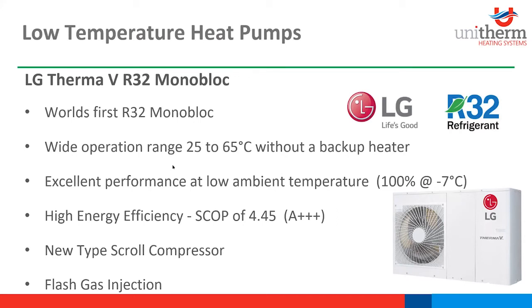So this is a flash gas injection, or wet vapor injection as it's also called. You're compressing at low temperature, low pressure, and you get up to a certain stage when you're reaching max compression, high temperature, high pressure, and then what it does is it gives it a wet vapor injection, which cools the compressor and allows it to compress even further, increasing the enthalpy dramatically on the thermodynamic cycle. So this is what gets you that extra, basically nearly 10 degrees or more from the thermodynamic cycle.